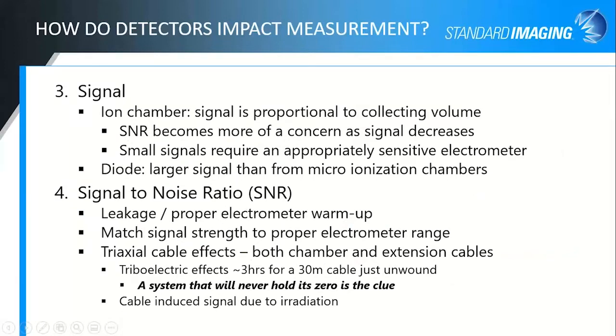Another way that detectors impact measurements, signal. If you are using, say, an ion chamber, your signal is proportional to your collecting volume. So as we try and make smaller and smaller ion chambers, your signal level does go down, which means your signal to noise ratio becomes much more of a concern as you get to these smaller chambers. You need to be extra careful to make sure you're correcting properly for leakage and other issues that come along with that low SNR as well. Small signals also require an appropriately sensitive electrometer.